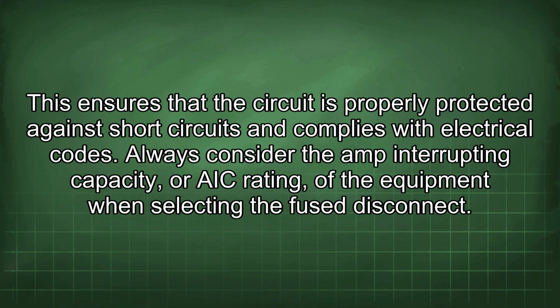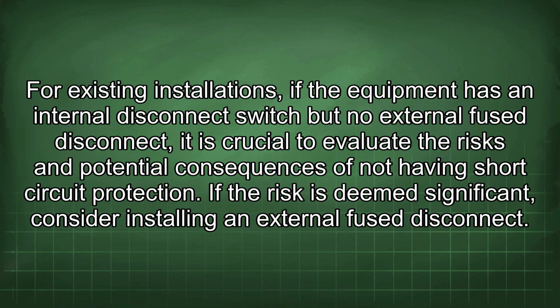This ensures that the circuit is properly protected against short circuits and complies with electrical codes. Always consider the amp interrupting capacity, or AIC rating, of the equipment when selecting the fused disconnect. For existing installations, if the equipment has an internal disconnect switch but no external fused disconnect, it is crucial to evaluate the risks and potential consequences of not having short-circuit protection. If the risk is deemed significant, consider installing an external fused disconnect.